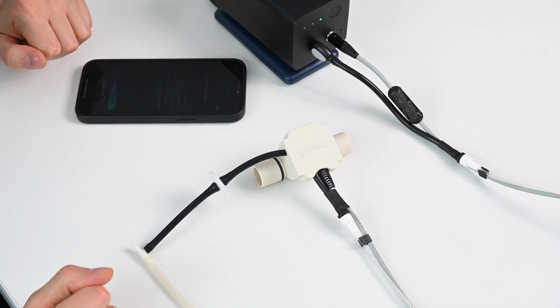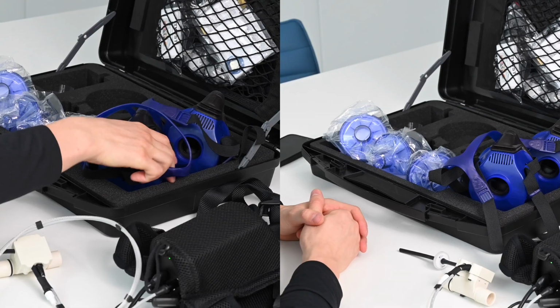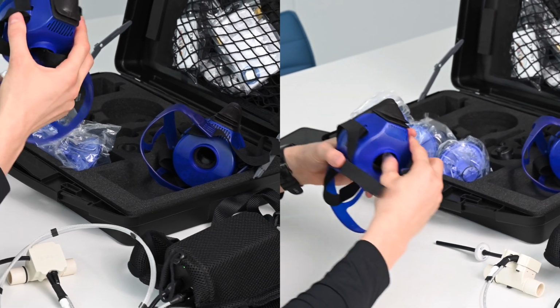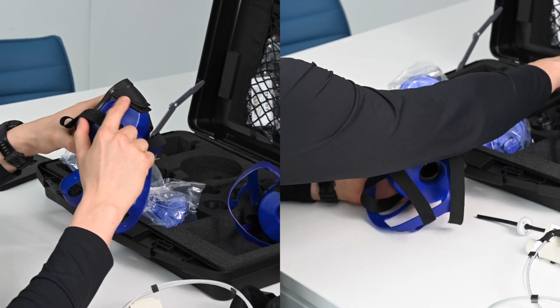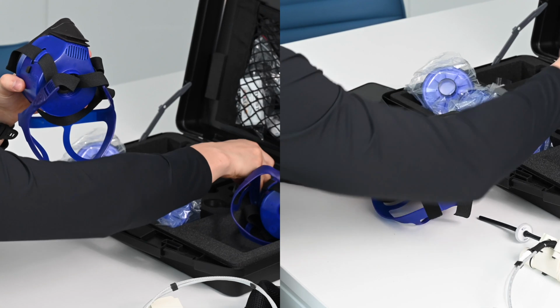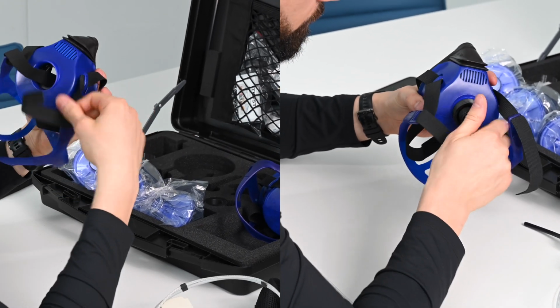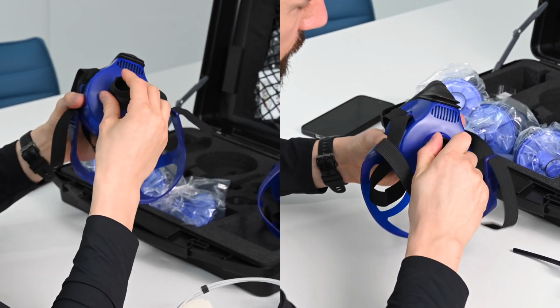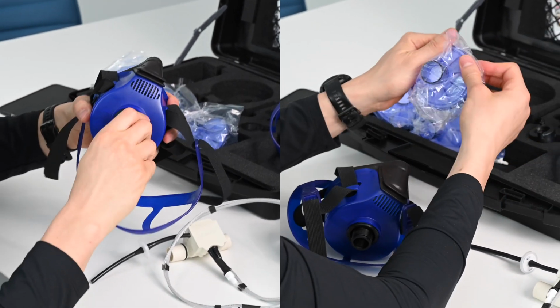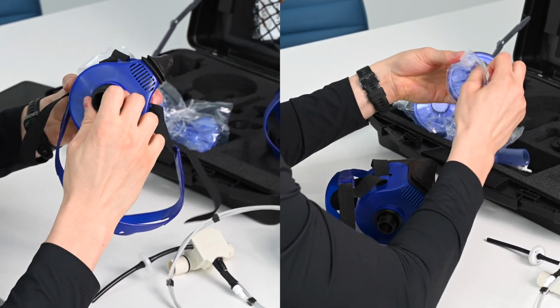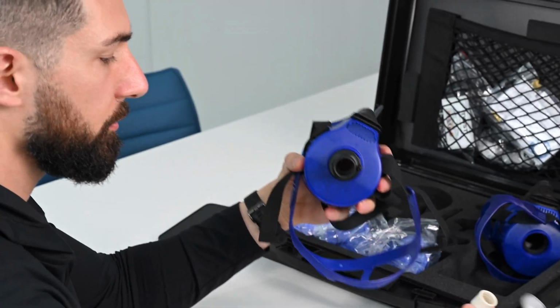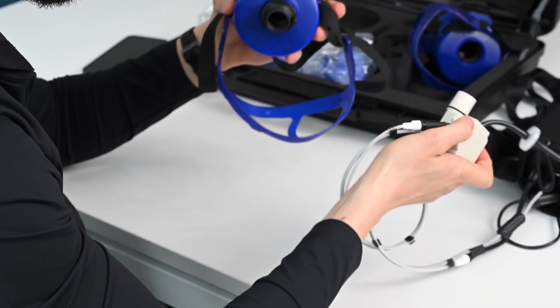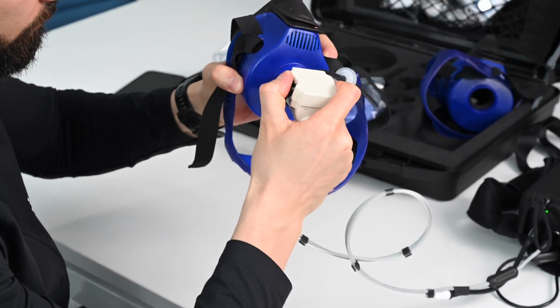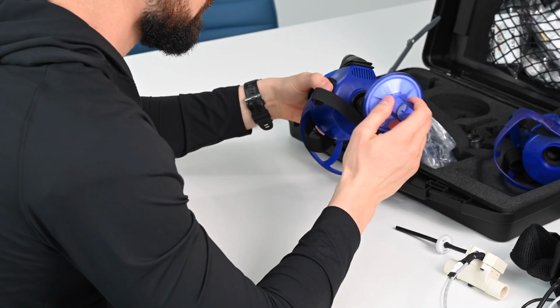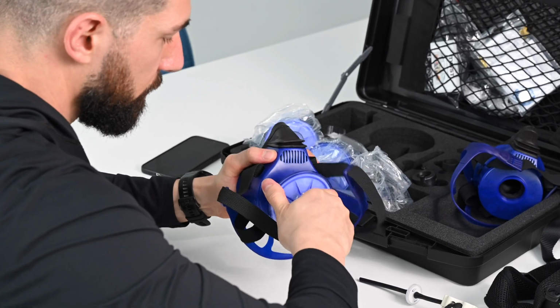Once the PNOE unit has been calibrated twice, it is time to connect the flow sensor to the mask. There are 2 different sized masks in your kit, one is a small medium and the other is a medium large. You can see this on the right-hand side of the mask if you were to be wearing it, on the black nose area. After choosing the correct mask size for the subject, there are 2 ways you can connect the flow sensor to the mask, one being the standalone mask adapter setup, where you do not use an antibacterial viral filter. The other setup is using an antibacterial viral filter.